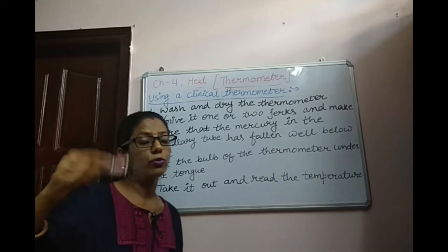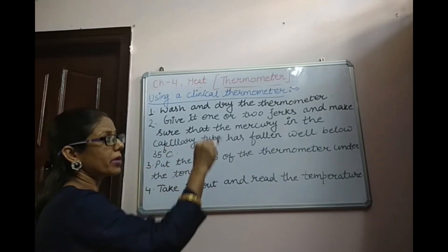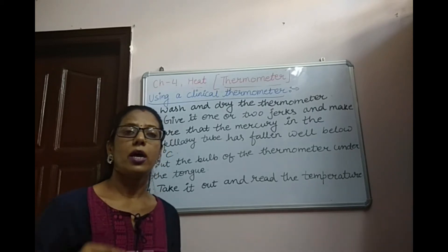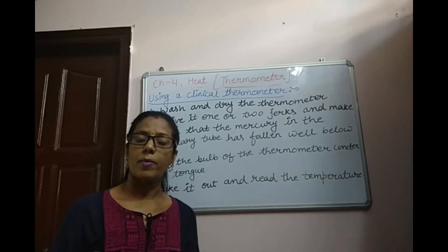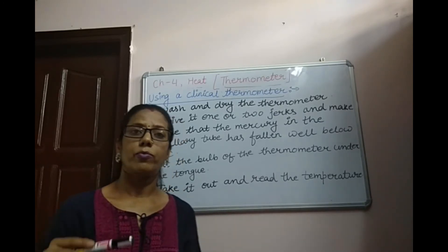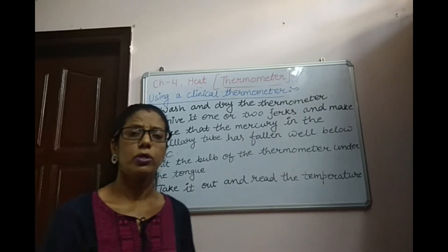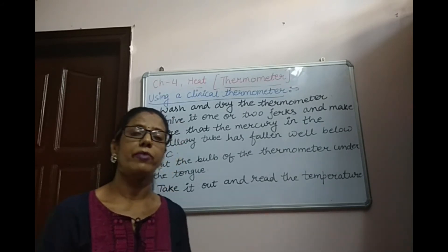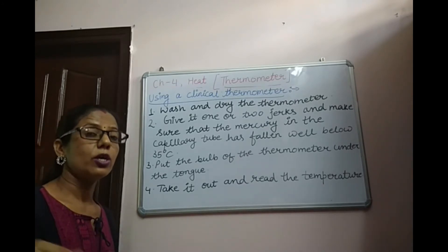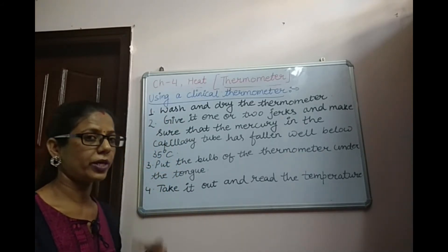Before using, we have to give jerks because the kink present above the bulb prevents the mercury level from falling back below 35 degree Celsius when we take the thermometer out of the patient's mouth. So by giving jerks, the mercury can fall below 35 degree Celsius and we can use the thermometer again.